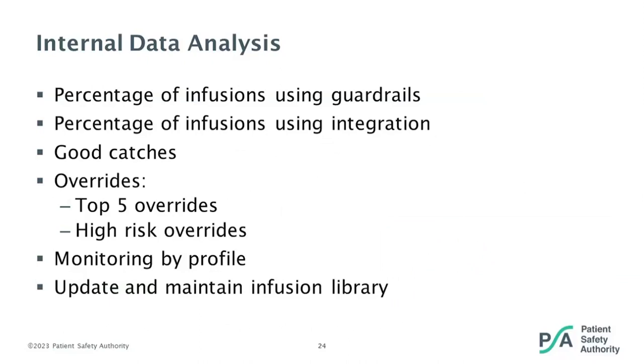Our organization is working on these goals. Some examples of metrics that may be useful to track include the percentage of infusions programmed with guardrails and the percentage programmed with EHR integration. Tracking good catches or near misses may also reveal areas of opportunity, as well as overrides — which may be broken down by library profile. As noted in the Joint Commission and ISMP guidelines, importance is placed on updating and maintaining the smart pump library.